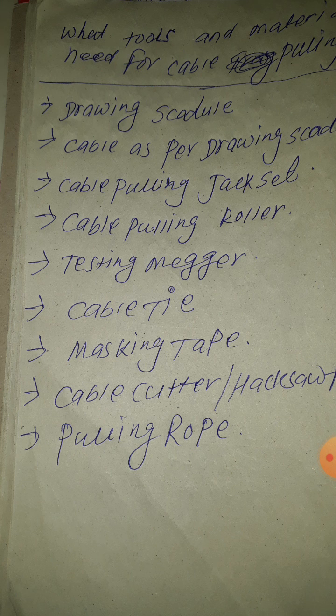And next one is the cable testing megger. You need a testing megger also. Before pulling you can test the cable, to see whether this cable is in good condition or not, whether the cable insulation is good, whether the core inside is good or not. You can check with the IR insulation test, and after that check the cores also, because the cable is going a very long way. One cable length may be more than 100 meter, 150 meter, like that.